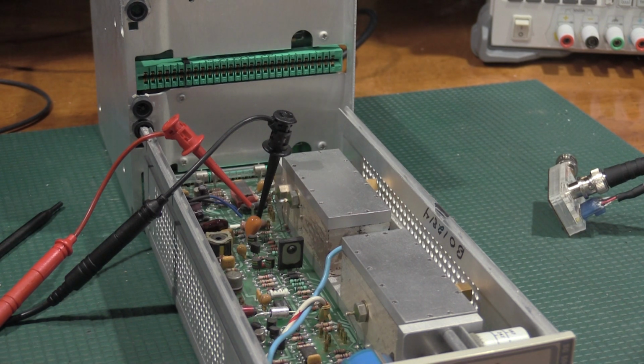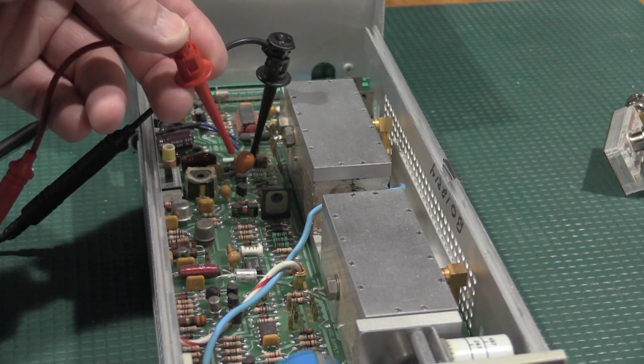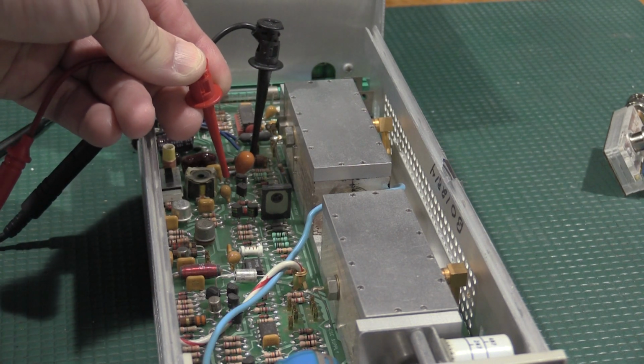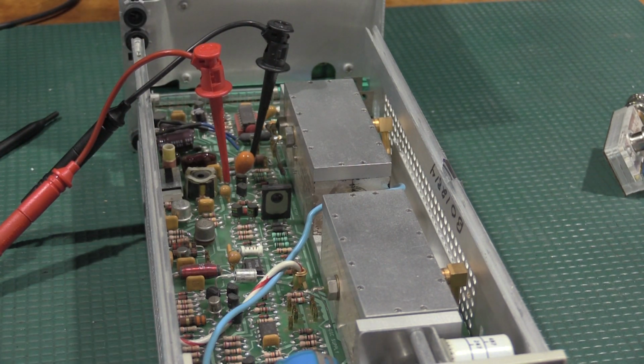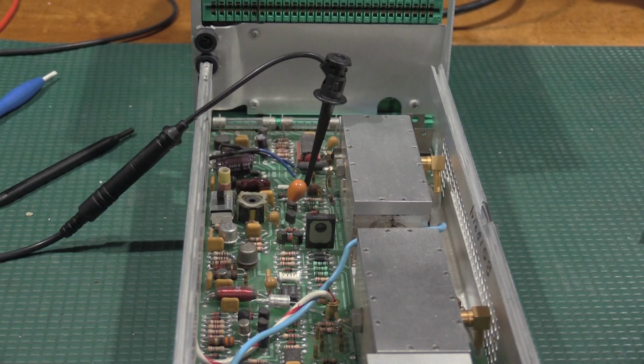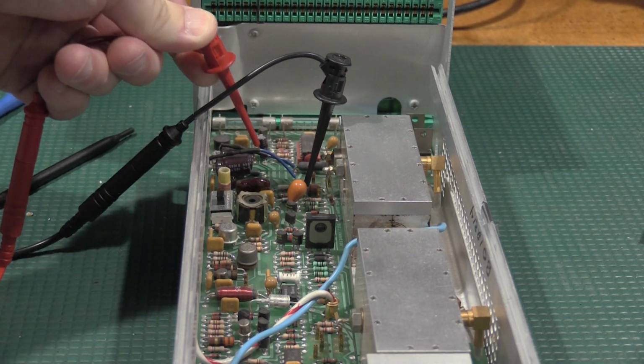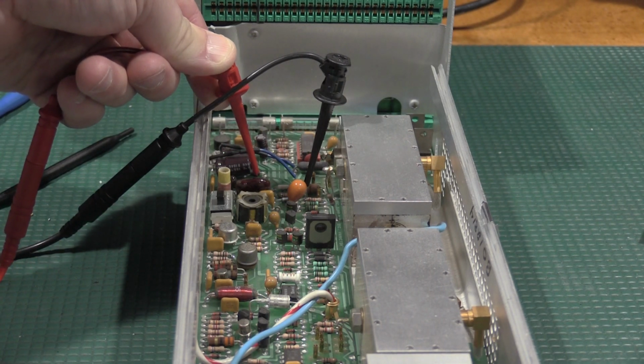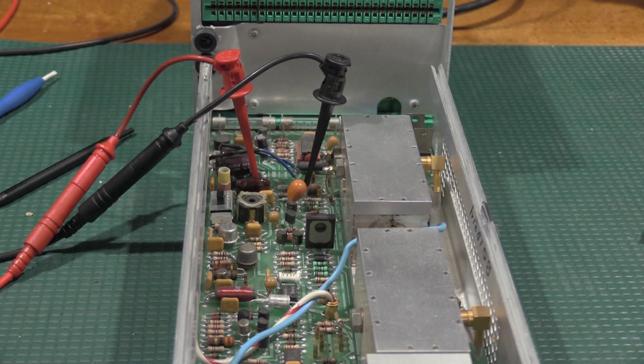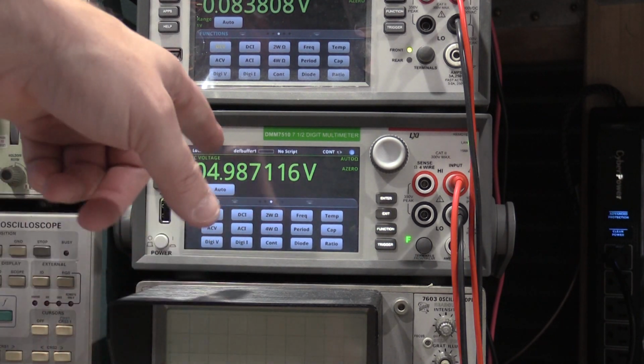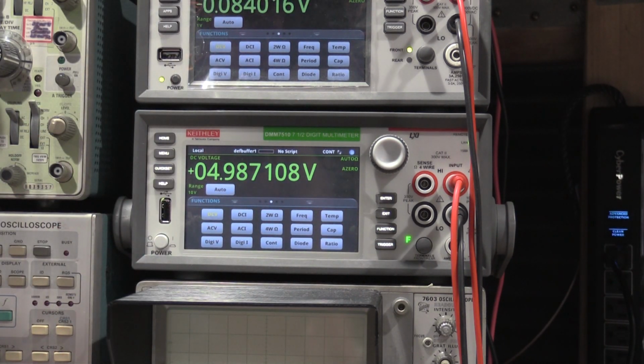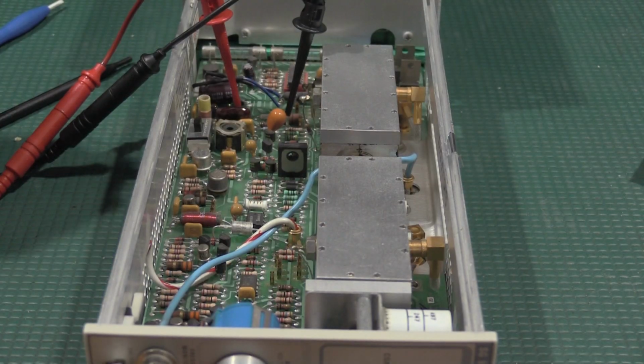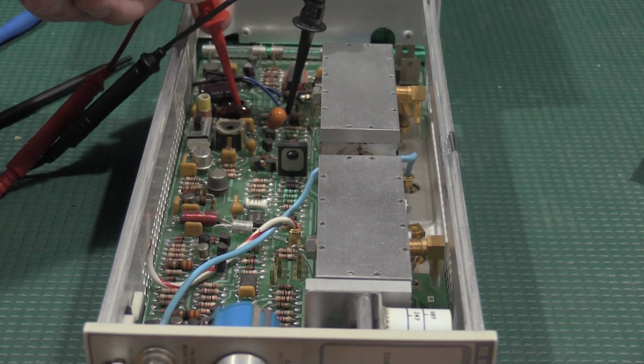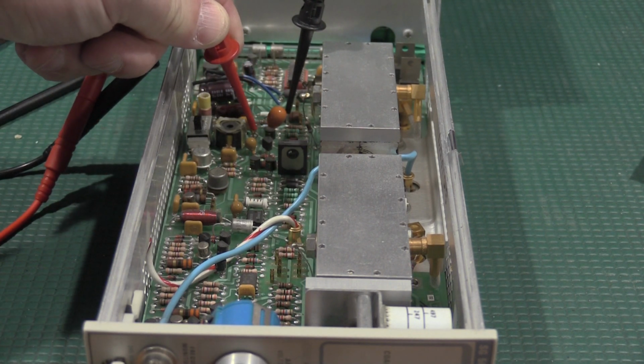And we've got to test the 5-volt supply, and I have a tolerance of 300 millivolts on that. The 5-volt supply test point is down here. Right there. No, it's not. That's test point 2. The 5-volt supply test point is right here. And we're allowed 300 millivolts. We're at 4.98, so the 5-volt rail is perfect. In step 3, we need test point 2, which is where we just were, over here.